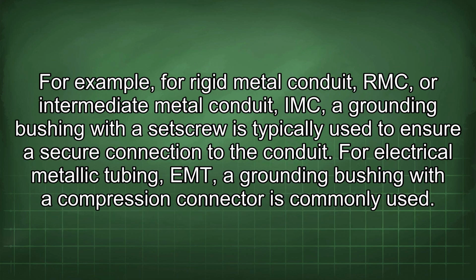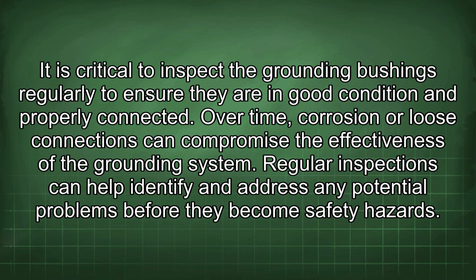For example, for rigid metal conduit (RMC) or intermediate metal conduit (IMC), a grounding bushing with a set screw is typically used to ensure a secure connection to the conduit. For electrical metallic tubing (EMT), a grounding bushing with a compression connector is commonly used. It is critical to inspect the grounding bushings regularly to ensure they are in good condition and properly connected. Over time, corrosion or loose connections can compromise the effectiveness of the grounding system. Regular inspections can help identify and address any potential problems before they become safety hazards.